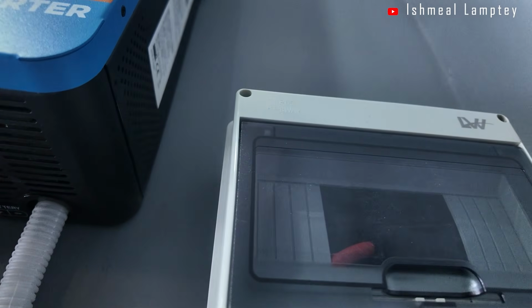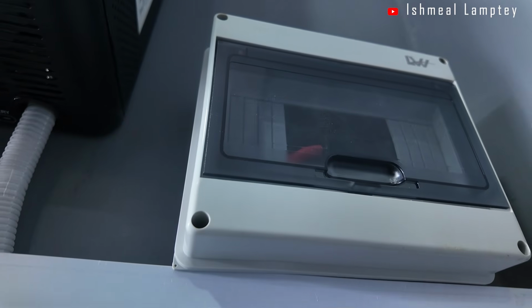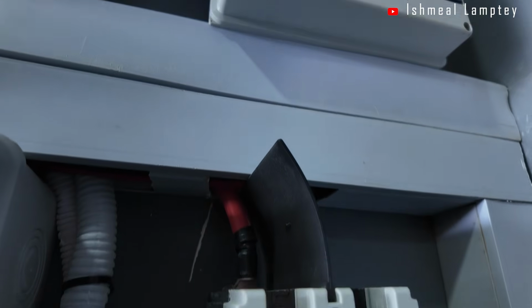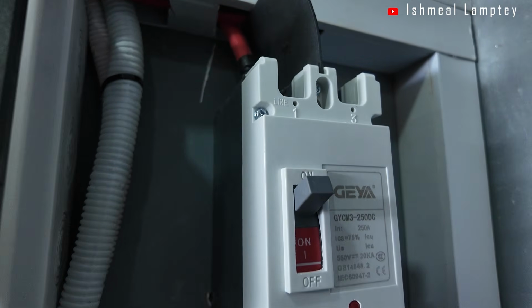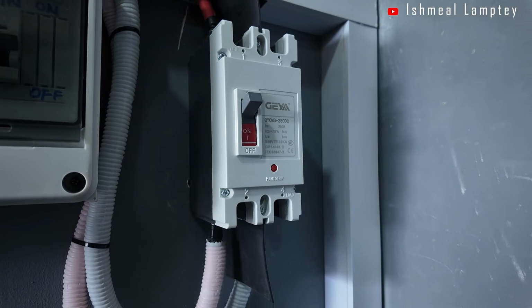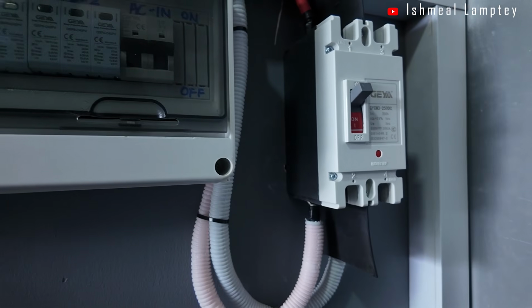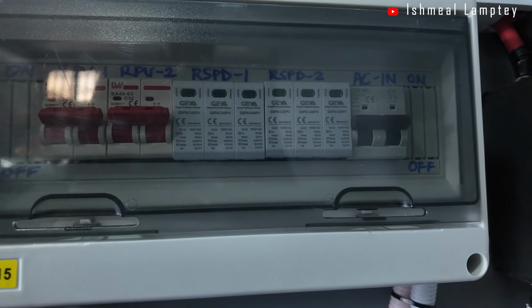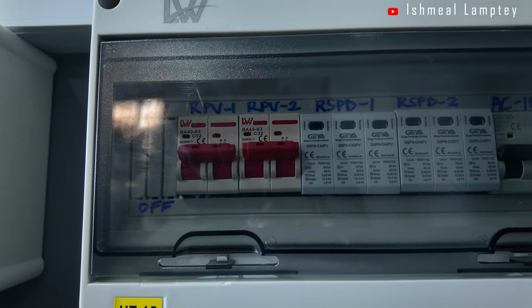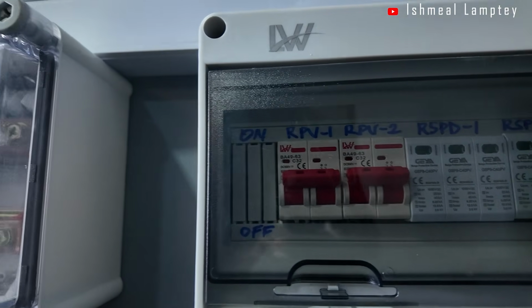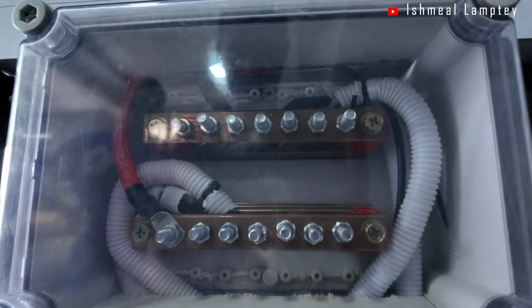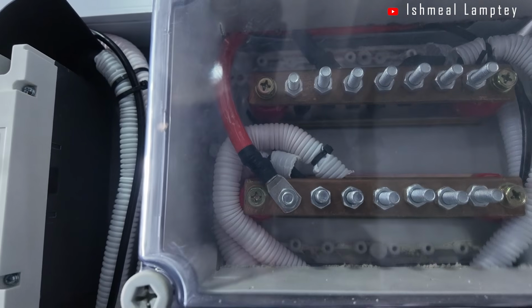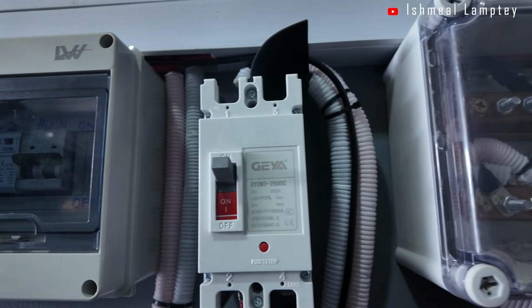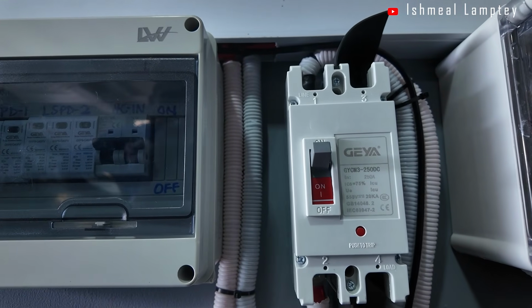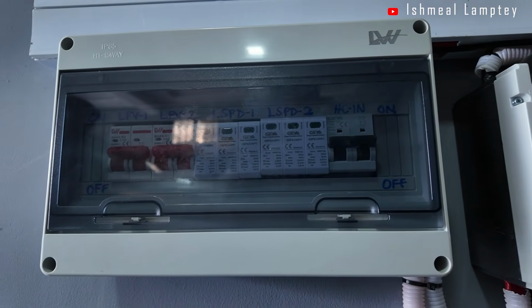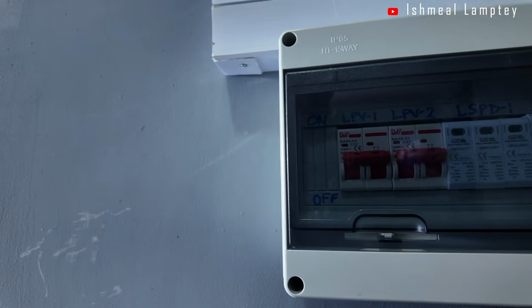So we did that, and then came to the point where I had to configure the inverter. On the inverter, you have configurations such as specifying the exact type of battery you're using - whether it's gel, flooded, or AGM battery. For this case, it was lithium battery, and lithium batteries have different modes - some with 15 cells, some with 16, 14 among others. This one was specified as 16 cells.